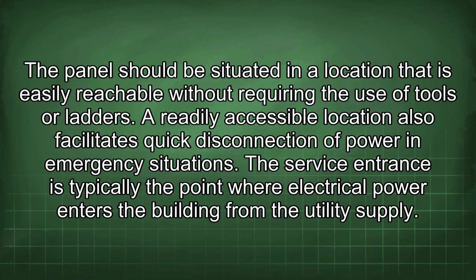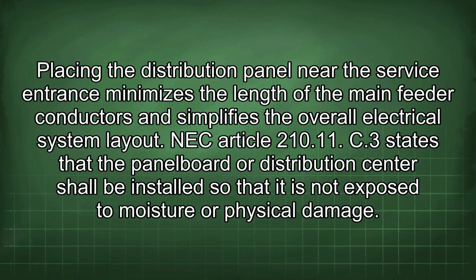The service entrance is typically the point where electrical power enters the building from the utility supply. Placing the distribution panel near the service entrance minimizes the length of the main feeder conductors and simplifies the overall electrical system layout. NEC Article 210.11.